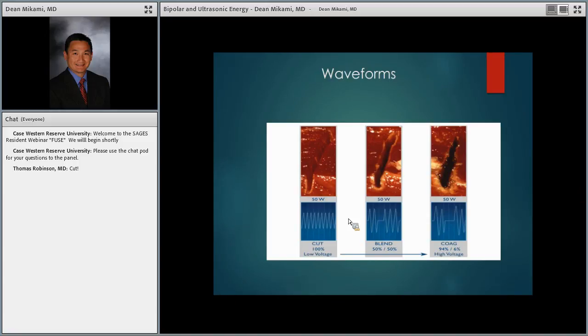So we're looking at these different forms, but once again, when you use the cut mode on your electrosurgical pencil, the blend mode is activated. So you really can't set the machine. When you set up your ESU, you're going to set 30 power on your cut, 30 power on your coag, but there's going to be a blend mode. Most pencils only have 2 buttons. So if you're setting it to a blend mode, when you hit the cut, the only effect you get is the blend mode. You don't get the pure cut mode. So that's an important clinical factor to remember.